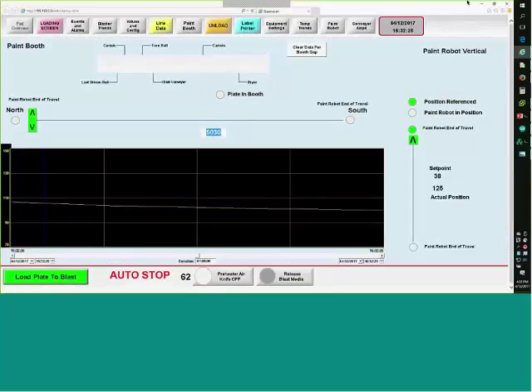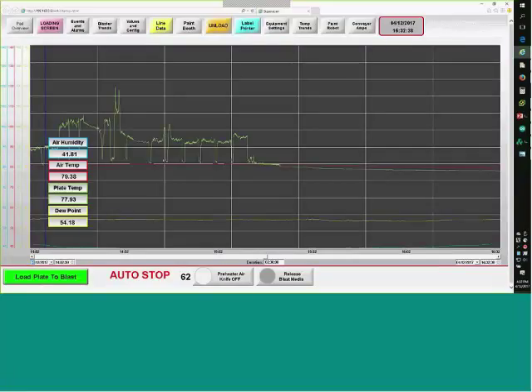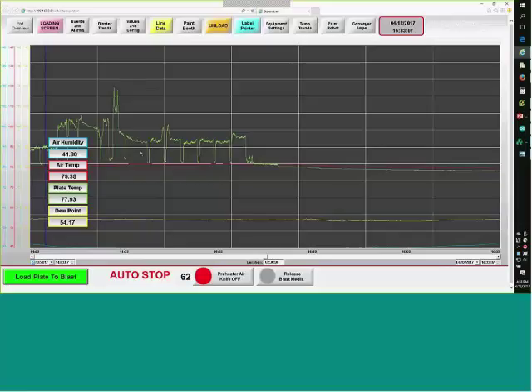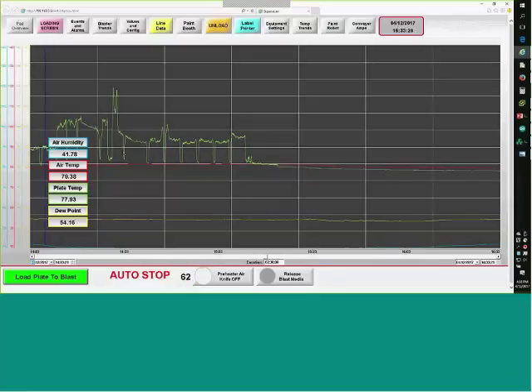The data from Indusoft is married to each plate. When a plate gets to the paint booth, a trigger from the PLC fires. The PLC knows the serial number of that plate and tells Indusoft, which saves the air humidity, temperature, and plate temperature — all of that is saved in the database for every individual plate as it's processed. There are about nine places through the process where we constantly save diagnostic information: when it was painted, where it was, everything about the system is stored.